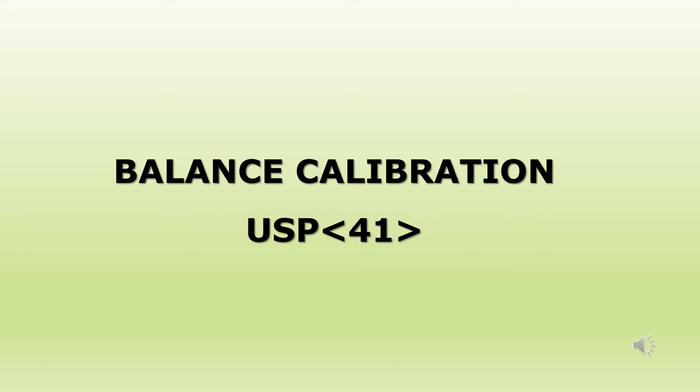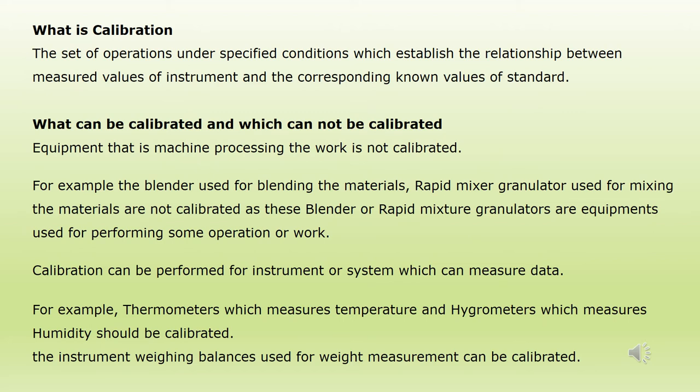Let us learn about the basics of calibration and all about weighing balance calibration, including questions which can be asked in interviews. What is calibration? Calibration is the set of operations under specified conditions which establish the relationship between measured values of an instrument and the corresponding known values of a standard.